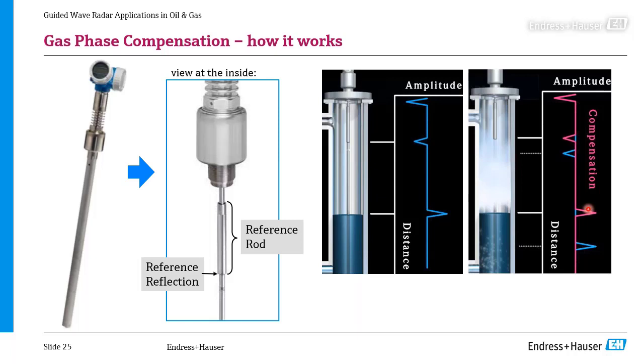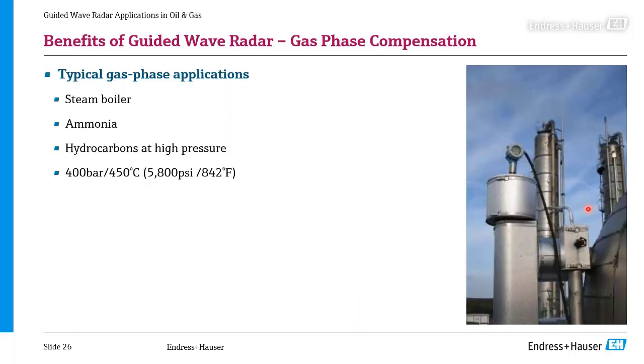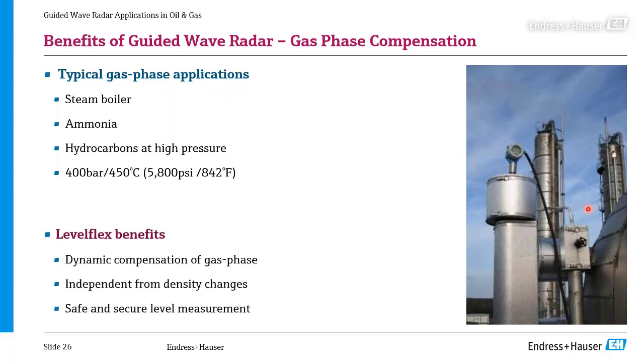Gas phase compensation, where can you use it? Typically steam boilers. Ammonia is a media that also causes a gas phase, and this gas phase slows down the radar signal, which causes a deviation. You can also see this with hydrocarbons at high pressure. If you have the Levelflex with dynamic gas phase compensation, it will compensate for this gas phase every second, not taking a minute but on the fly every time. So you really have a safe and secure level measurement in such applications.